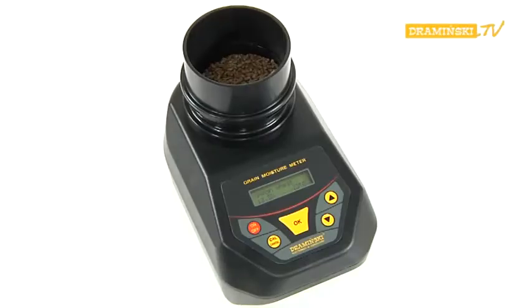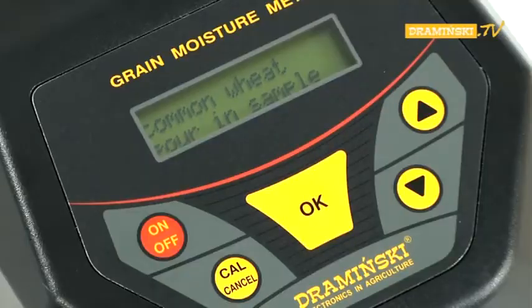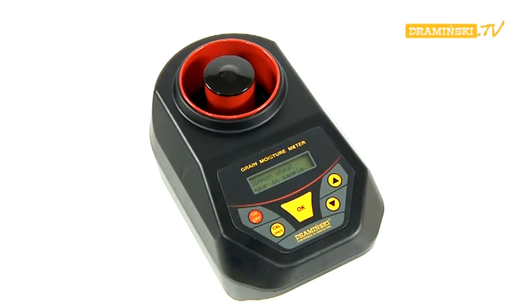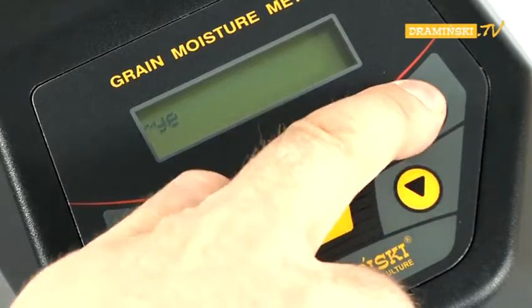After a while, the result of measuring the moisture as a percentage and the temperature in degrees Celsius will be shown. After the measurement, the chamber should be emptied and the OK button pressed. The command 'pour-in sample' will appear once more on the display, meaning you can repeat the measurement of the same sample or check the humidity for another sample. To select another species of grain, press the CAL button and repeat all the steps starting from the choice of the grain name.